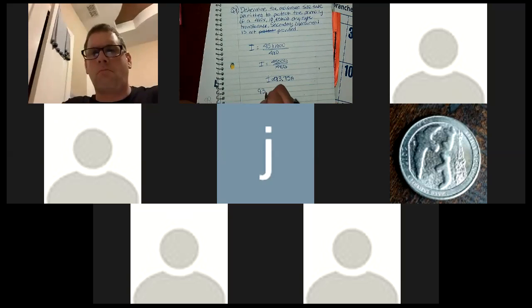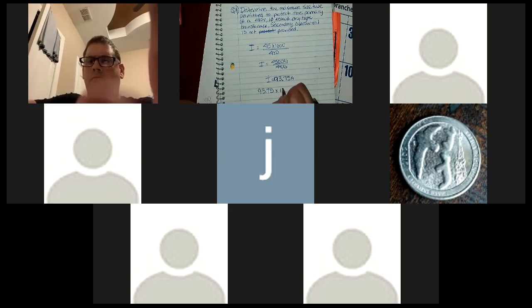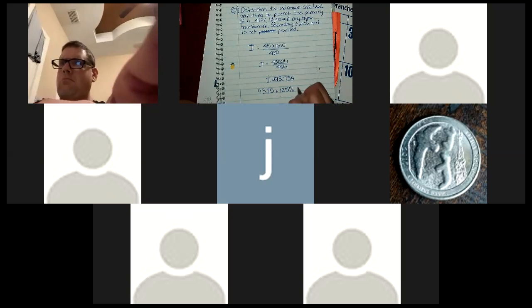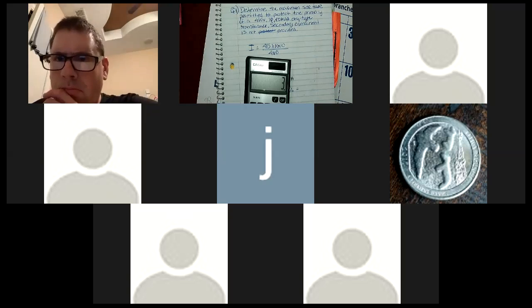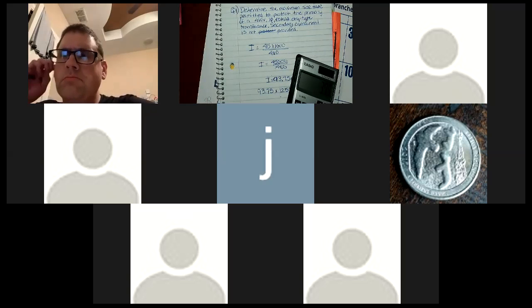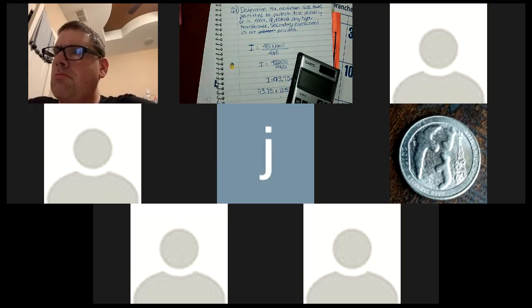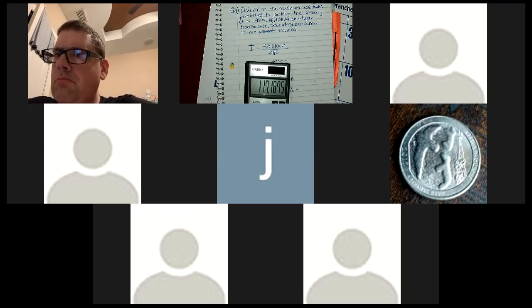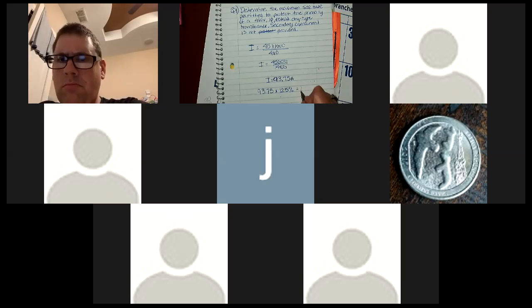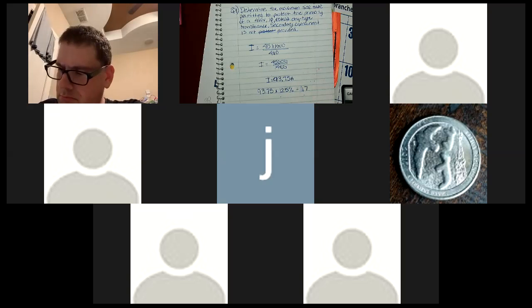So right here, I have 93.75 times 125%. 93.75 times 1.25, I get 117.18, 19, something like that. 117, that would be 19 right there.